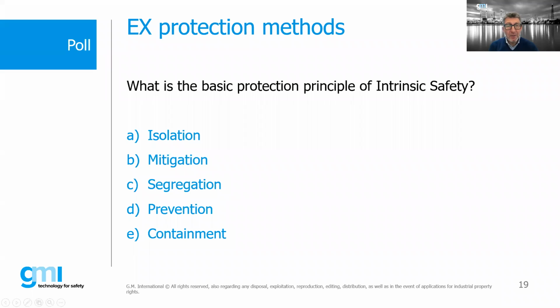While our guests answer that question, Bob, there's a live question. Let me ask you. Can you repeat what is increased safety? Yeah, increased safety is called EXE, and a good example is where we take a junction box with a bunch of terminal blocks on the inside. Increased safety more or less states that if we have our terminations on the inside of this enclosure separated by certain creepage and clearance requirements, and that these terminals, due to normal in-service operation, will not loosen up, meaning that they have some sort of locking mechanism, then as long as we maintain certain creepage and clearance requirements between energized circuits and there's no arcing and sparking going on, that's the concept of increased safety. It means that the enclosures we would use in a hazardous location can be, for example, a sheet metal enclosure or a plastic enclosure.